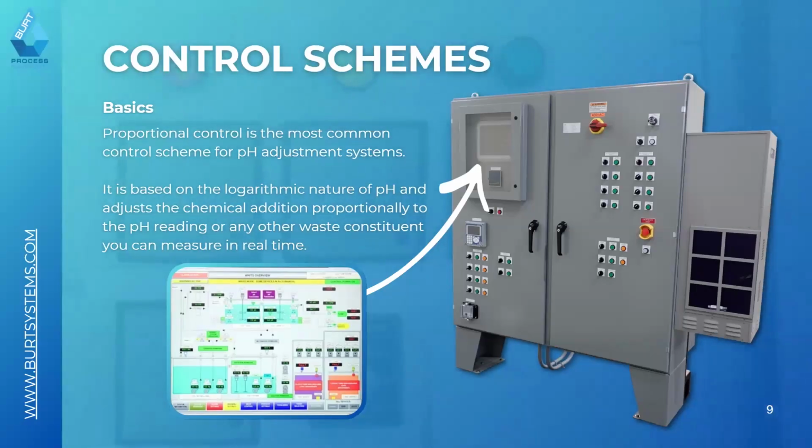So what you're really pulling out of the control scheme here is alarm sequencing charts. You're pulling out that data for tracking. You're monitoring its overall condition, because really every single drain point in your building, outside of some specialty waste, is going to come through this system. So it does become a critical utility in some ways, because it ultimately is the last choke point for your facility to operate. That's why there are a lot of different control suites, Allen Bradley, Siemens. A lot of this can be driven based on what the client's ultimate building integration system is.